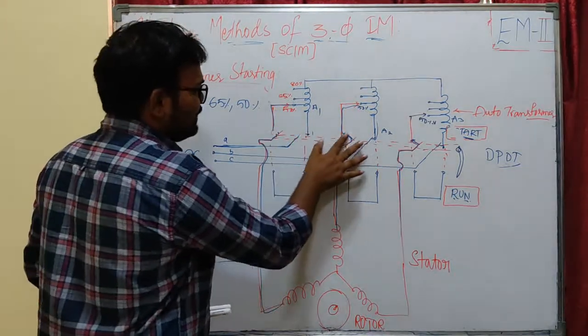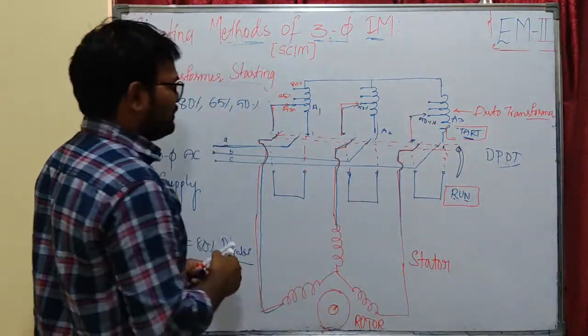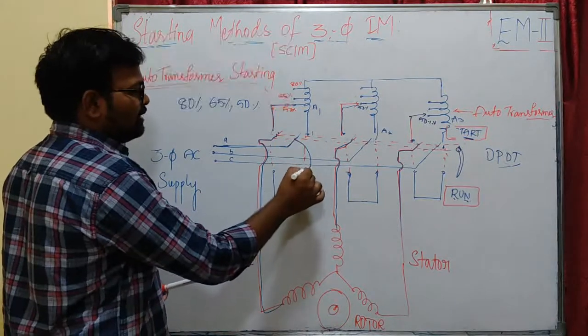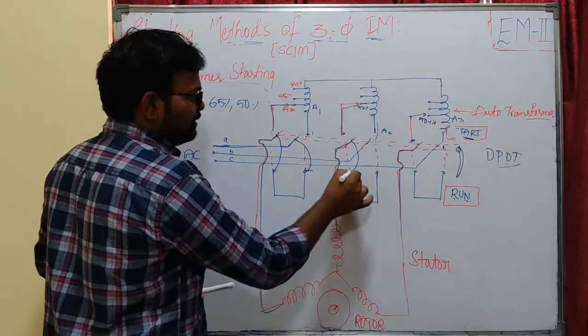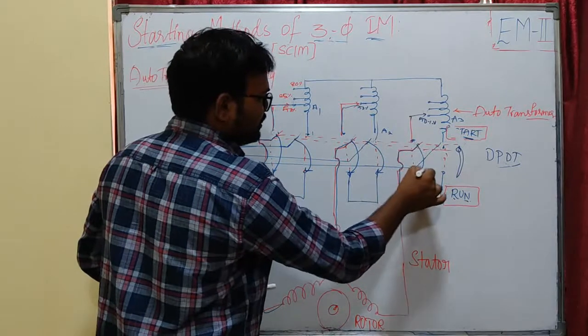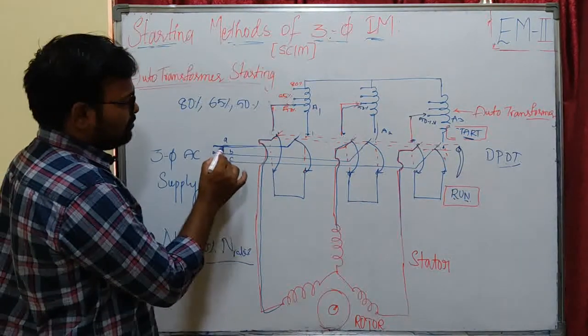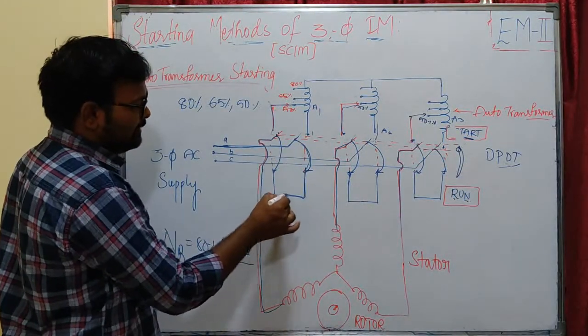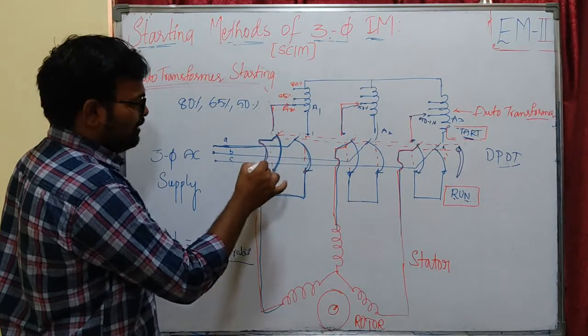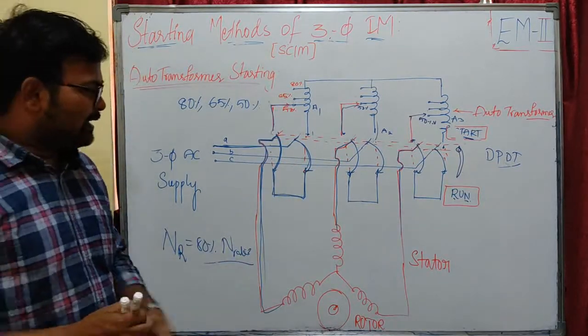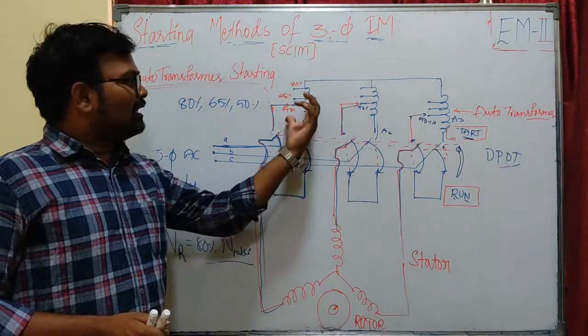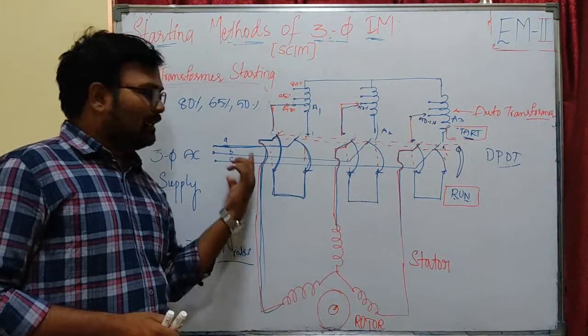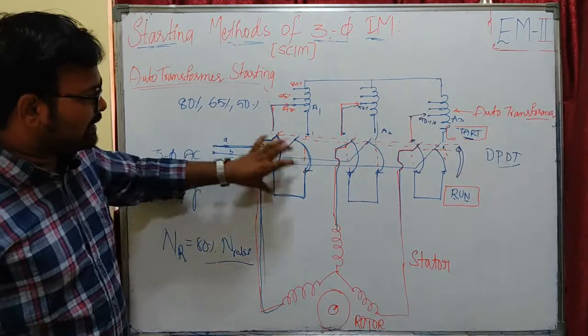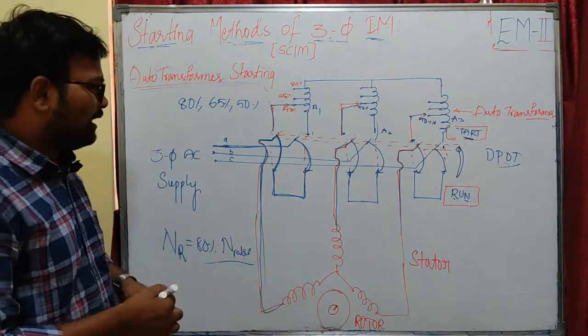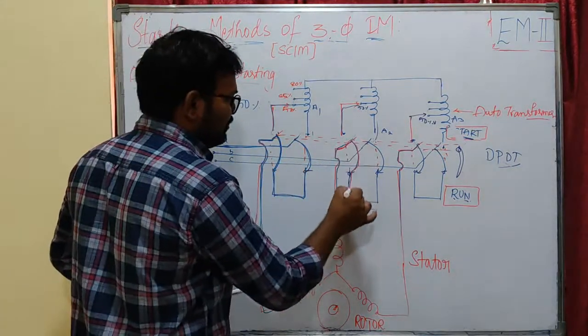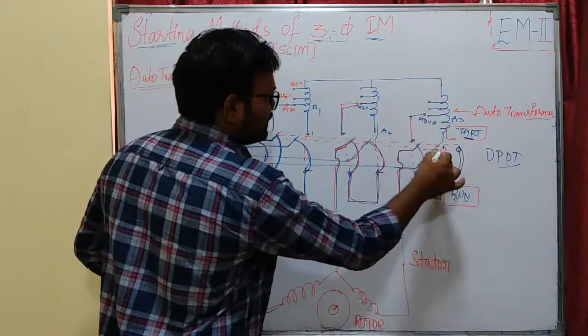Initially these two are connected. Now here this and this will connect, this way this will get connected. The circuit will be switched to this position. That means you can see my A phase is going like this, and it is short circuiting the auto transformer, and it is connecting to my stator winding. That is, we have disconnected our auto transformers from the stator and supply voltage, and the supply voltage is directly connected to our stator winding. Our auto transformers are bypassed here. I can say they are bypassed. The C phase is like this.